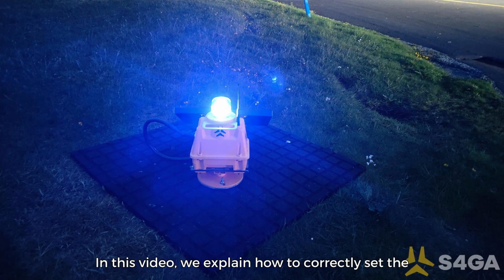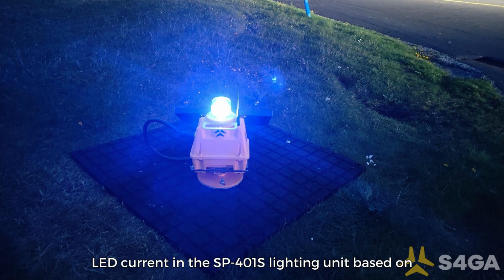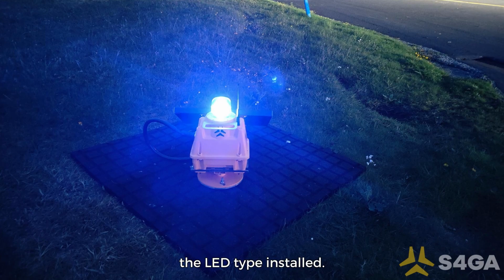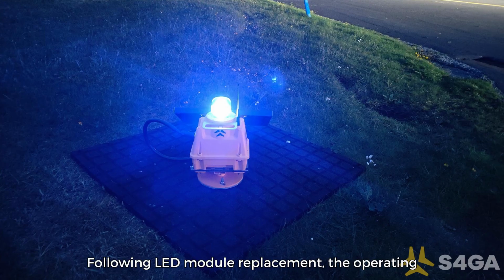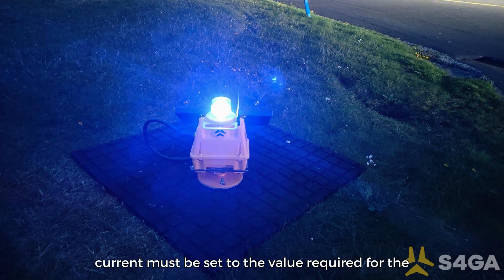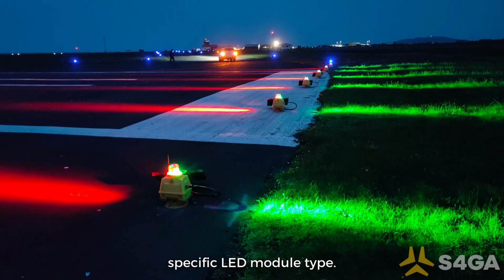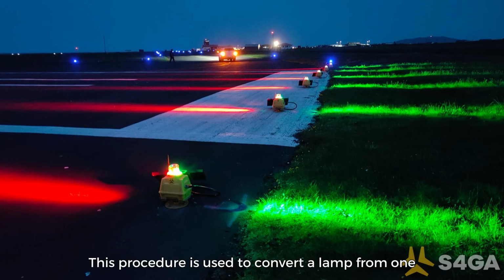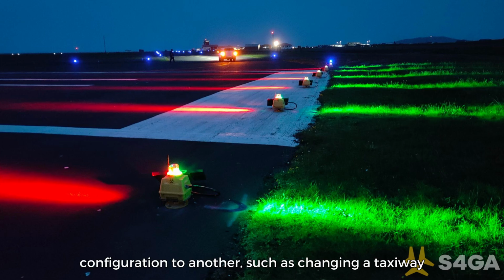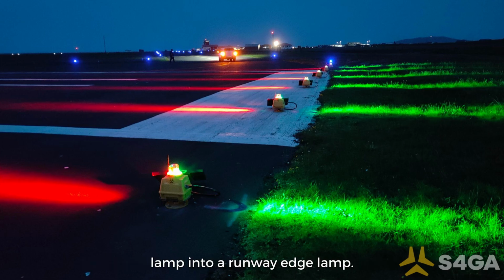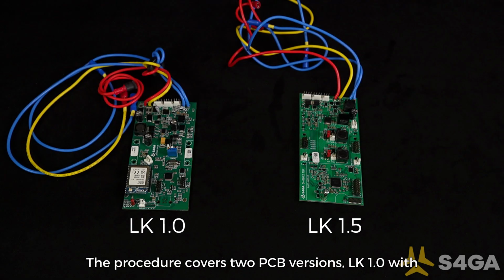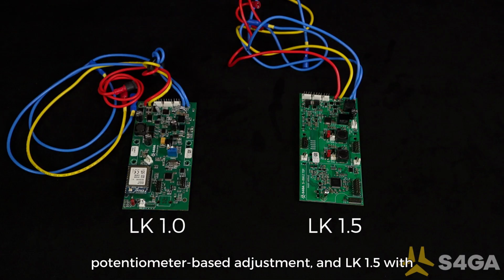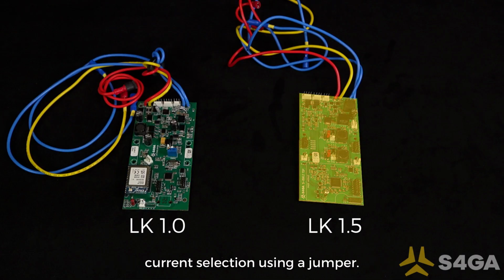In this video, we explain how to correctly set the LED current in the SP-401S lighting unit based on the LED type installed. Following LED module replacement, the operating current must be set to the value required for the specific LED module type. This procedure is used to convert a lamp from one configuration to another, such as changing a taxiway lamp into a runway edge lamp. The procedure covers two PCB versions, LK1 with potentiometer-based adjustment, and LK1.5 with current selection using a jumper.